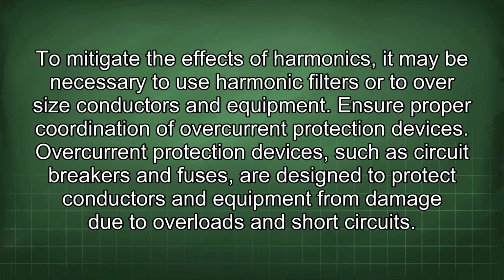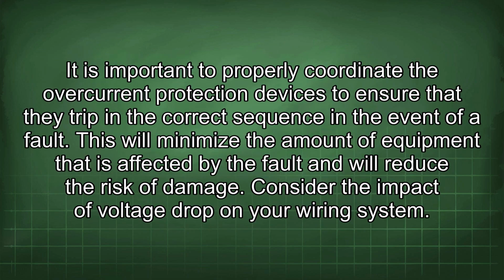Ensure proper coordination of overcurrent protection devices. Overcurrent protection devices, such as circuit breakers and fuses, are designed to protect conductors and equipment from damage due to overloads and short circuits. It is important to properly coordinate the overcurrent protection devices to ensure that they trip in the correct sequence in the event of a fault. This will minimize the amount of equipment that is affected by the fault and will reduce the risk of damage.